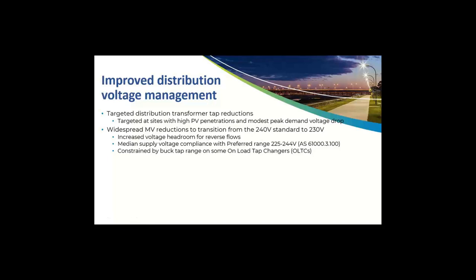This has, however, been constrained on many of our on-load tap changers at our zone substations, which transform voltages down to 11 or 22,000 volts, due to the limited buck tap range. Most of our on-load tap changers have traditionally been procured for peak demand requirements, and so they sometimes have limited buck tap range for reverse flows.